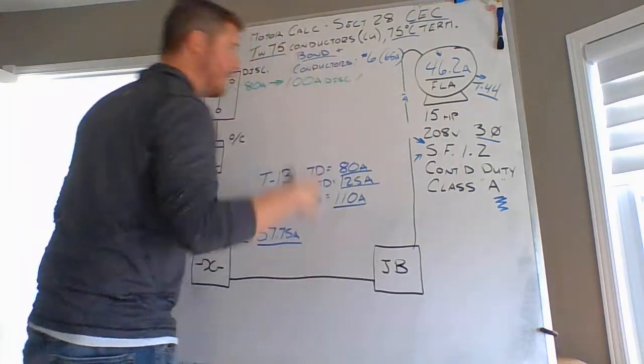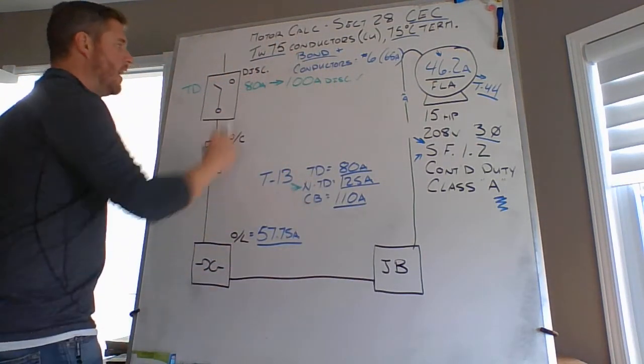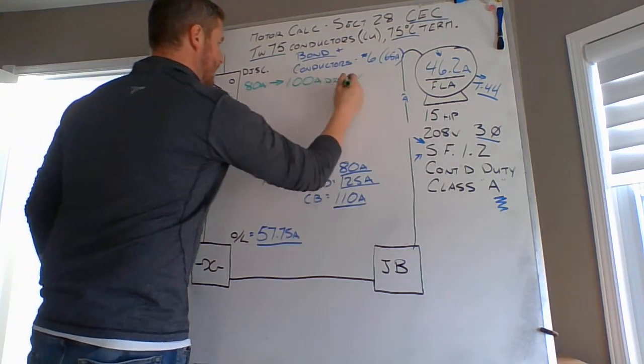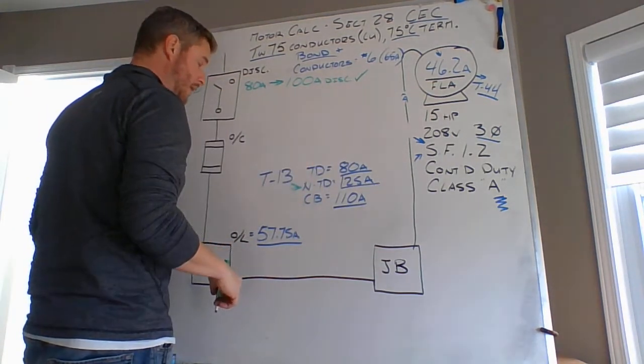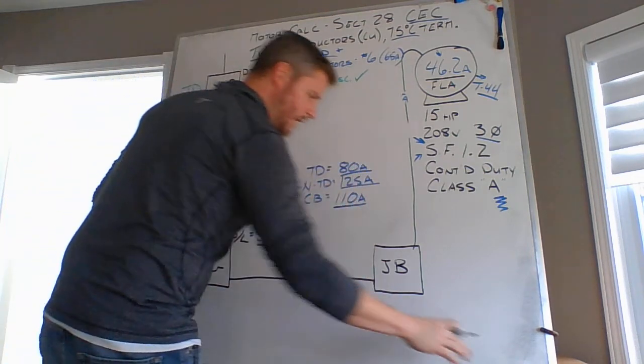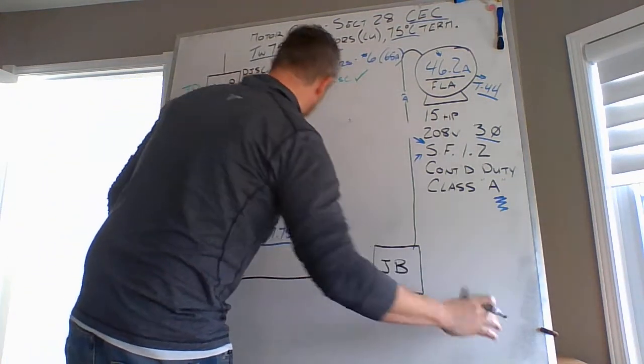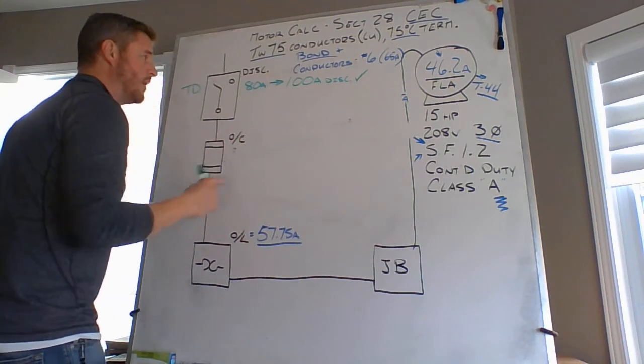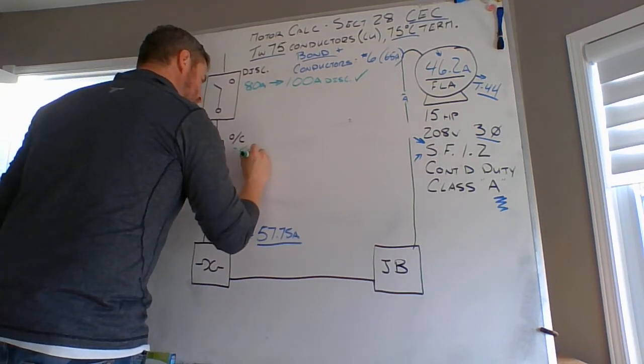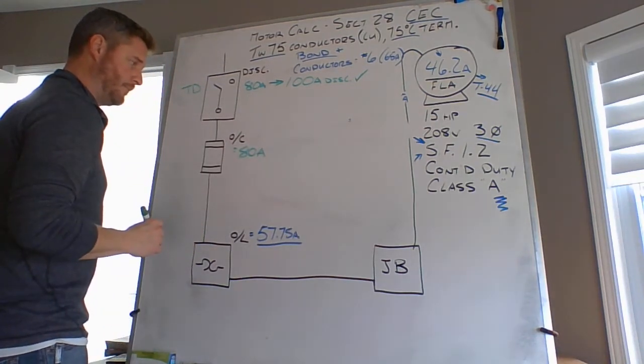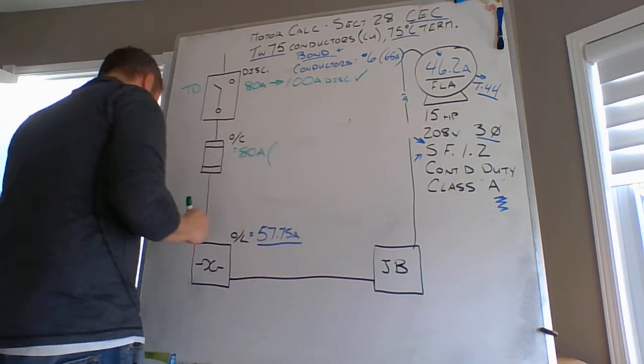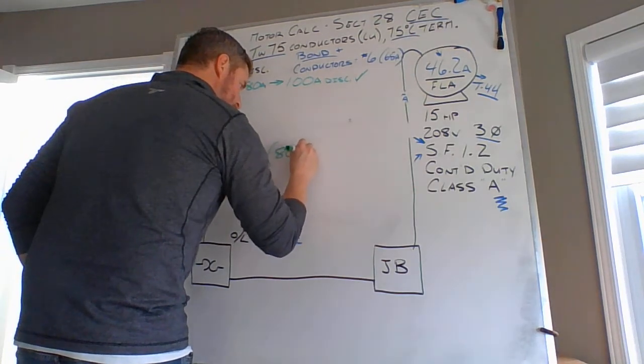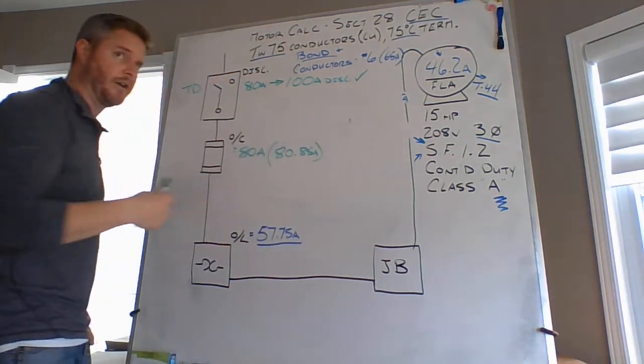We'll get rid of the circuit breaker thing, because this is probably more of the common value that you would do for an installation for a motor like this. 80 amp fuses inside of a 100 amp disconnect, that's a big check mark right there. You've done that calculation correctly. And we can eliminate these down here. We don't have to necessarily worry about our different types of overcurrent devices. We know our conductors that are being installed. So at this point in time, our overcurrent device is calculated for a time delay value at 80 amps installed. Or what we actually calculated for that overcurrent capacity to be was 80.85 amps calculated.